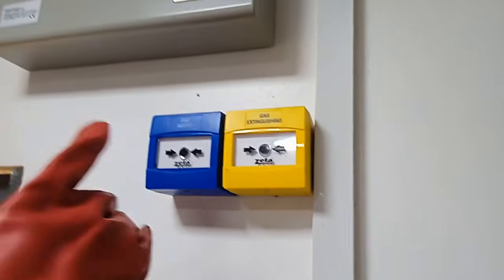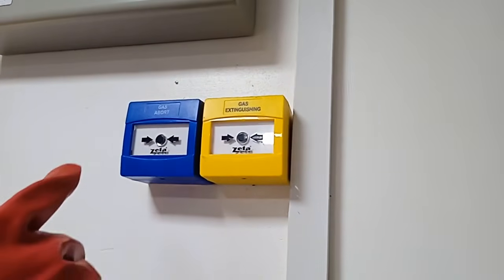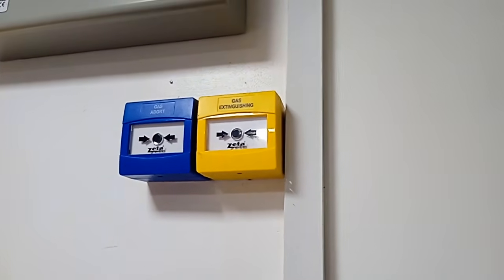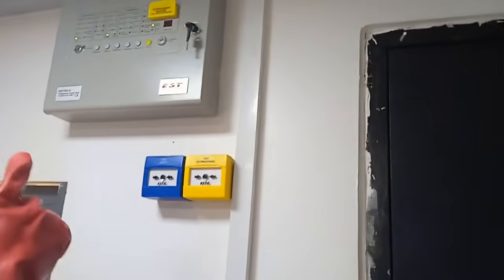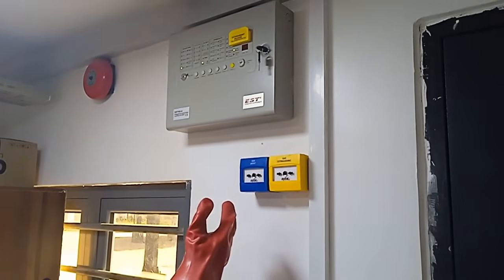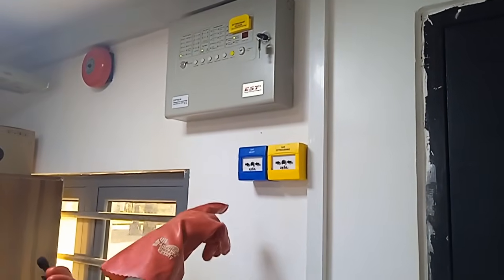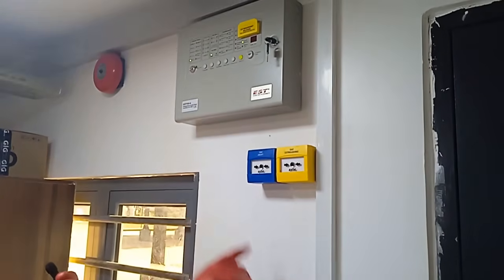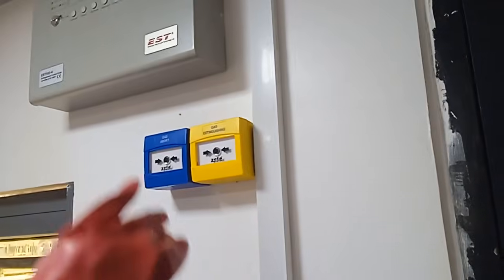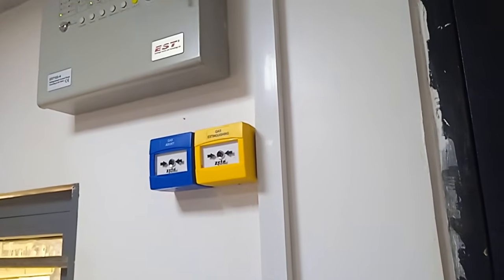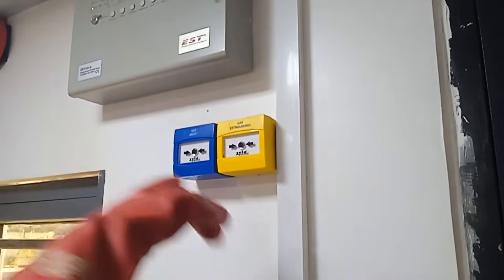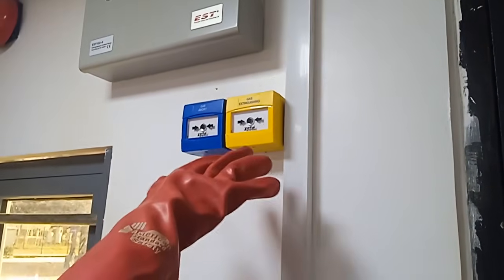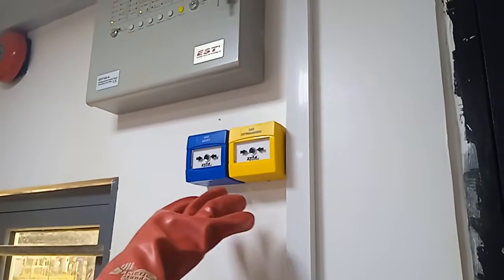The blue one is for you to abort the gas. Let's say for example that there is smoke inside this place and the control panel wants to discharge the gas. Somebody that is around at that moment can press this button to stop the gas from discharging. That is the gas abort. Then in case you come here and see that the control panel has not taken care of the fire, you can press this button immediately to discharge the gas. These two buttons help you to handle the fire manually.